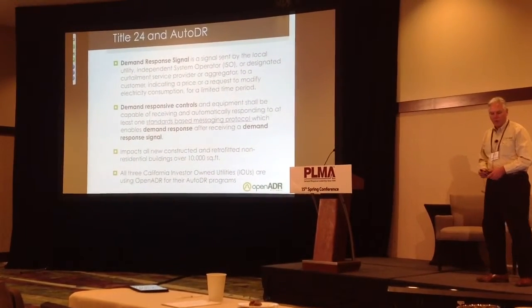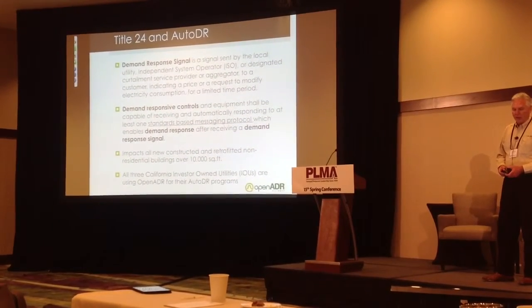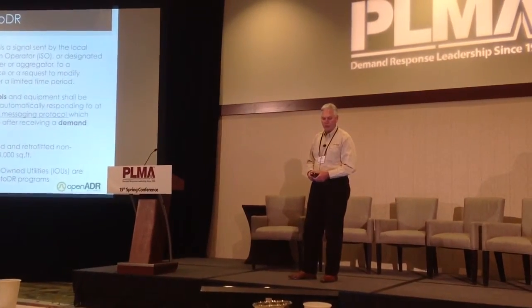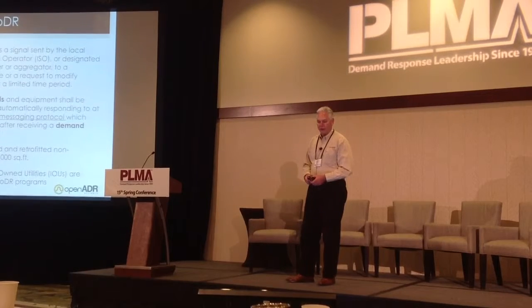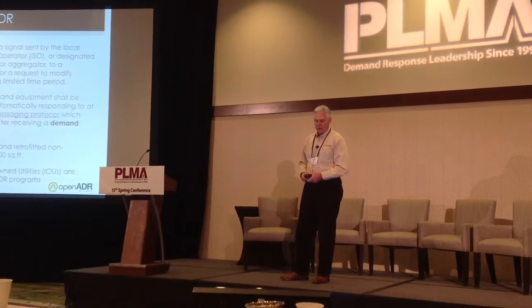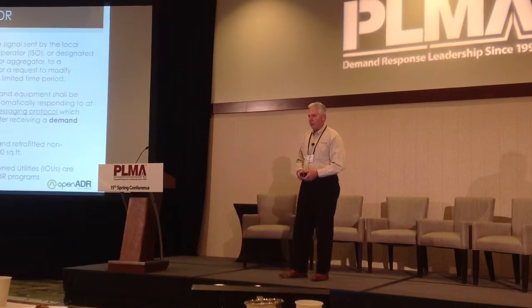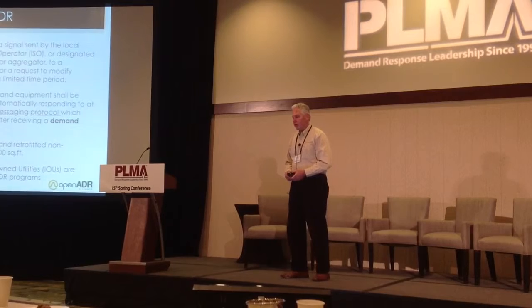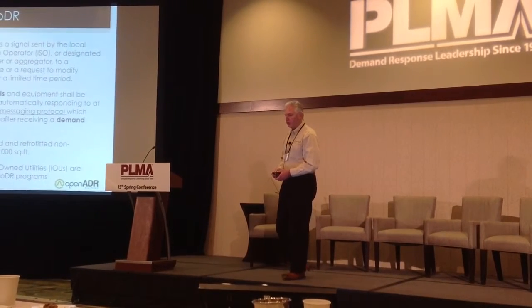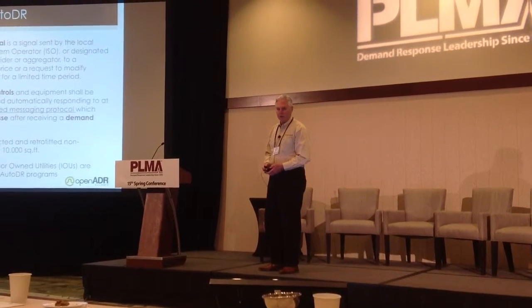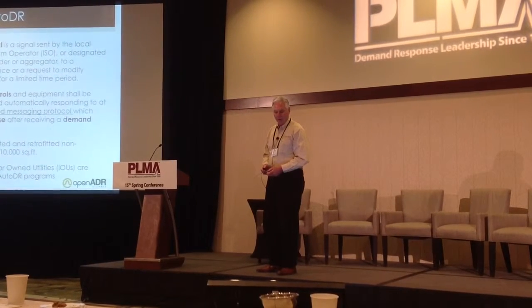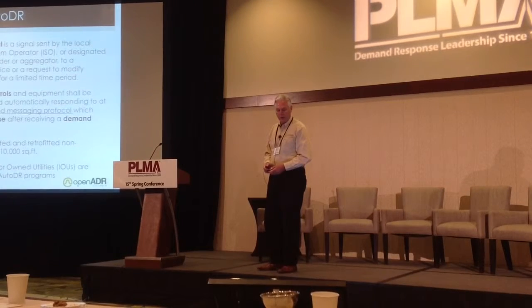The code change defines a requirement for equipment to be able to receive a demand response signal and to affect demand response controls. This code change impacts every newly constructed building over 10,000 square feet, as well as significant retrofits to buildings in that same range.